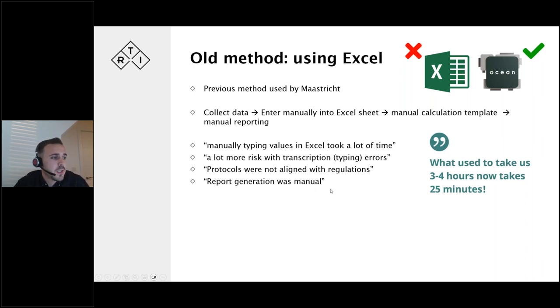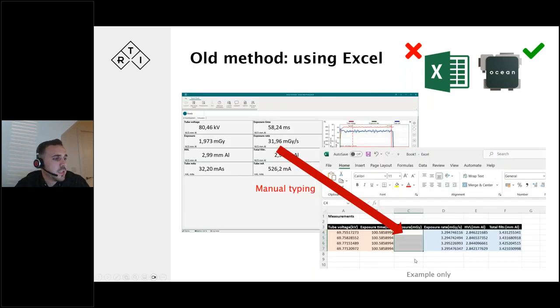That's what it would take an engineer to go up to the system, find the right Excel database. This isn't an exact Excel workbook, just an example to show you — I'm sure you're familiar if you've performed this in the past. Making an exposure, taking out specific values and typing it into a huge Excel sheet. If you get things wrong or a calculation fails, traceability is very difficult. And as soon as you take it out of the software, it's very difficult to validate who, when, where, and with what device the measurements were performed. So that's a big issue.